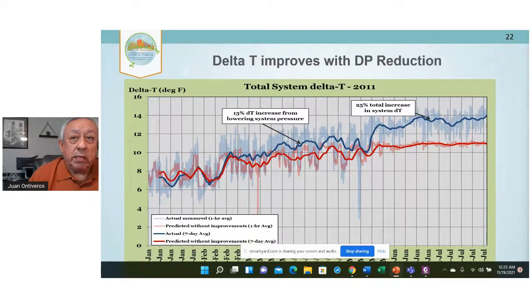in 2011, without improvements, by lowering the pressure, we saw a 13% to 25% improvement in delta T. If you improve your delta T, you're improving the effectiveness of your chiller, and in our case, also significantly improving the performance of the cooling tower, of the tanks. So this was a very big deal. We could see that in the initiative.